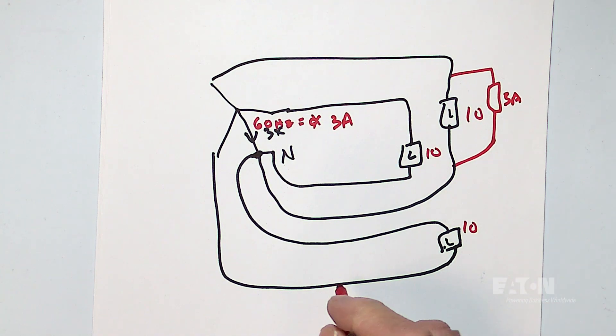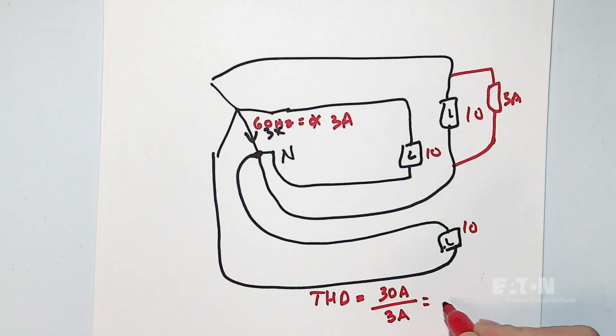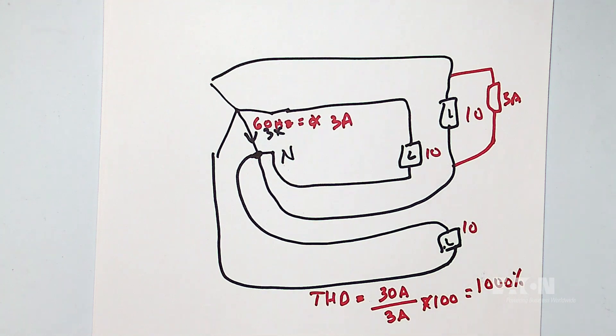So how do we calculate THD? THD is all the harmonics added together. And in this case, it's 30 amps. We'll ignore everything else. Divided by the fundamental. So now I have times 100%. So now I have 1000% distortion on my neutral.